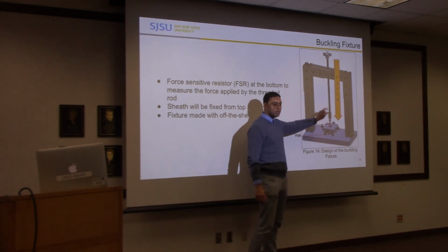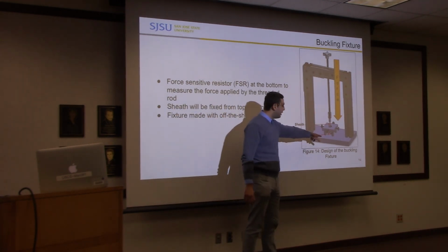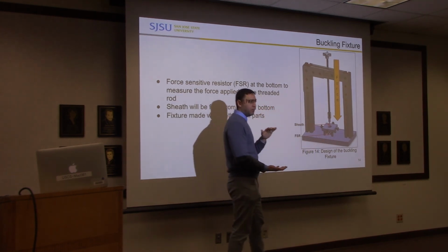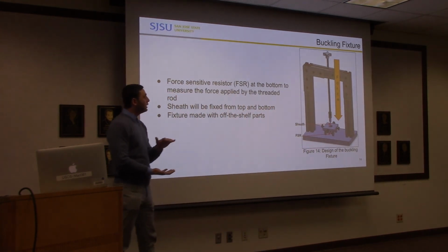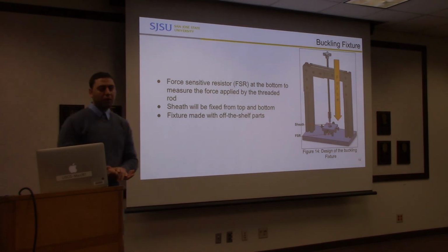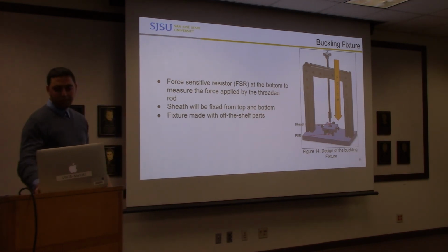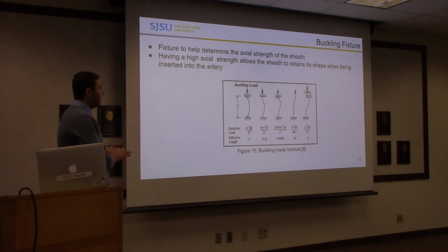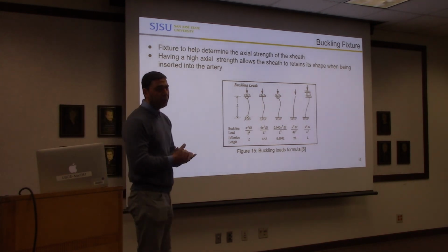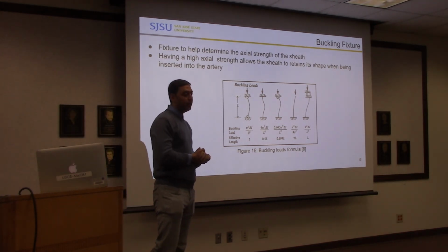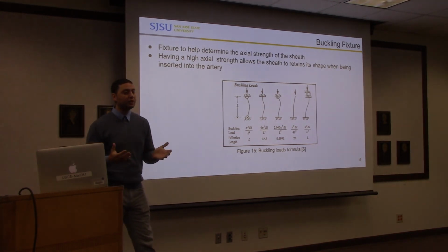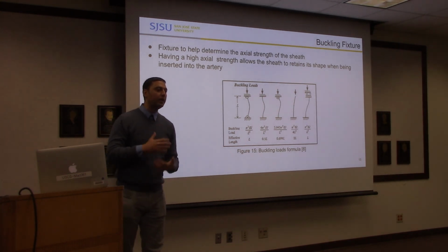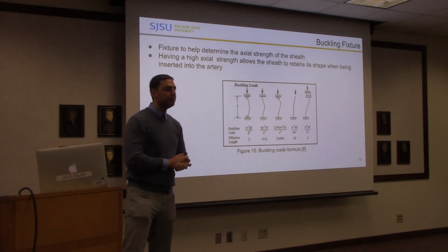How do we measure the force we're applying? We have a sensor at the bottom to measure the force applied on the sheath. And we will go over how to record the data as well. So before we go there, why are we doing buckling? To ensure that the sheath that we're designing can withstand the axial forces that we'll encounter in the operation.